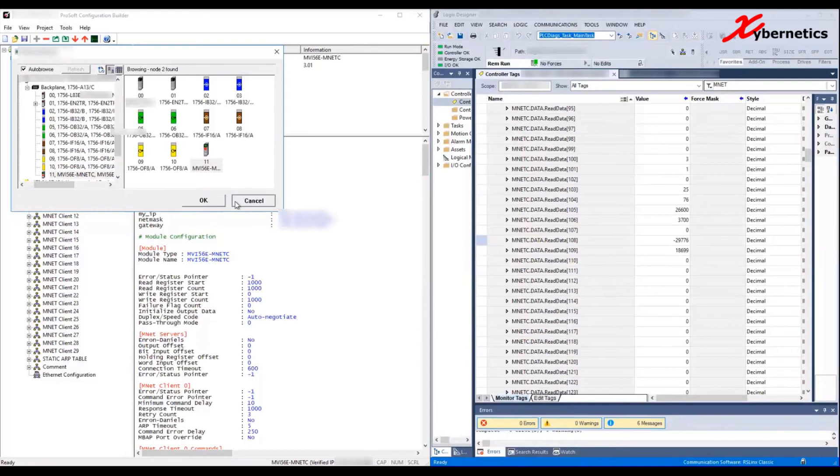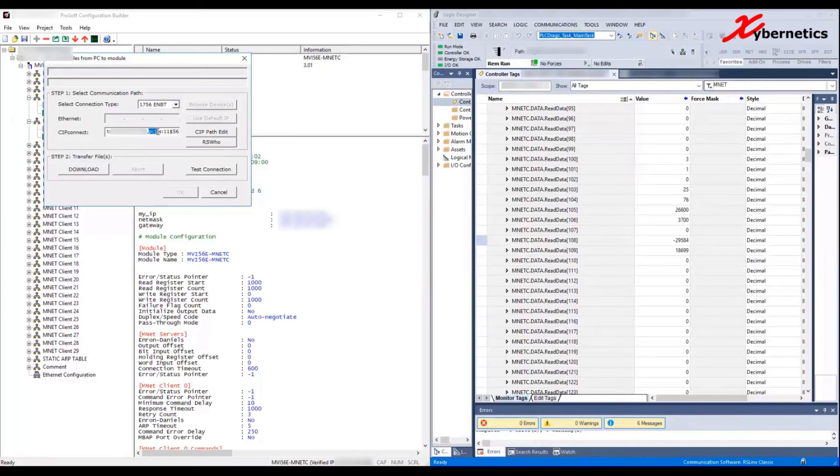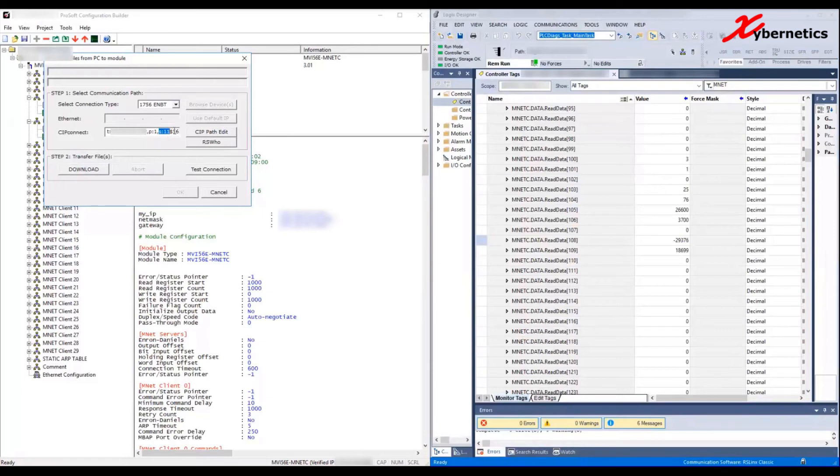Once you click OK, it will give you that. The first section is your IP address of the Allen Bradley PLC - that's one thing you have to be clear. The second section tells you P1, which I believe is Processor 1. If I'm wrong, please leave a comment below. S11 is your slot number, which is slot 11, and MVI56 I believe is the MVI56 model number itself.